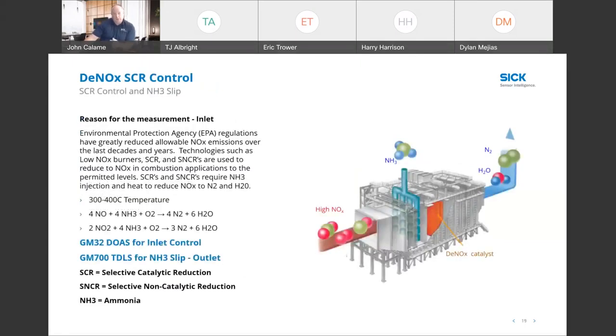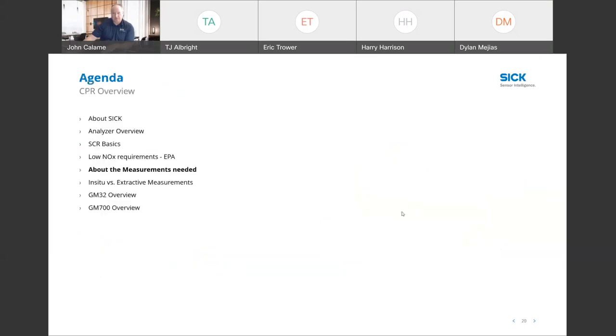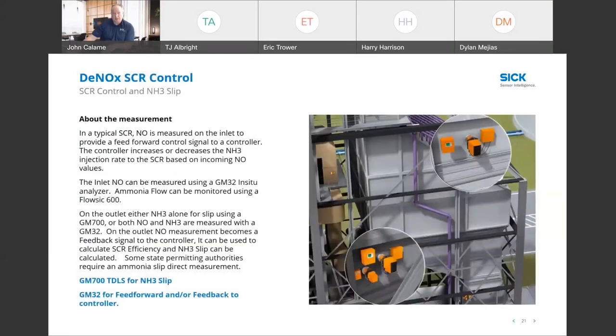So the SCR control ammonia slip, this is a way that we can, a picture's worth 1,000 words. So you've got your high NOx that's coming in from your stack. It's going into the SCR, and then you're injecting your ammonia prior to your catalyst bed, and then it's reacting and converting the NOx to nitrogen and moisture, which are benign components that are naturally occurring in the environment. So that's the basic premise of how the SCR, SNCR work.